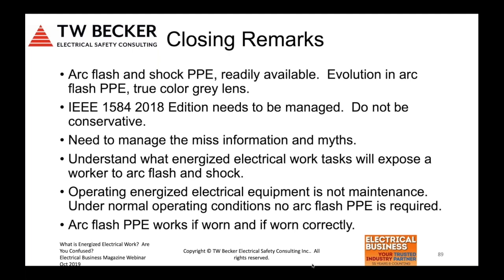We need to manage the misinformation and myths. It's going to take us down a rabbit hole in industry, and we don't want to go down that path. Working energized and the risk related to it can be managed where the risk residually is as low as reasonably practical and the worker can proceed. If we continue with the misinformation, it's going to actually contribute to increasing the likelihood of occurrence, because we're going to get qualified electrical workers that lose confidence, and they're going to have a human performance problem with human error probability going up. Not good.